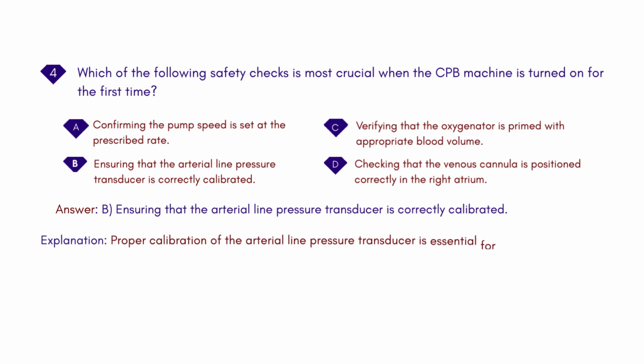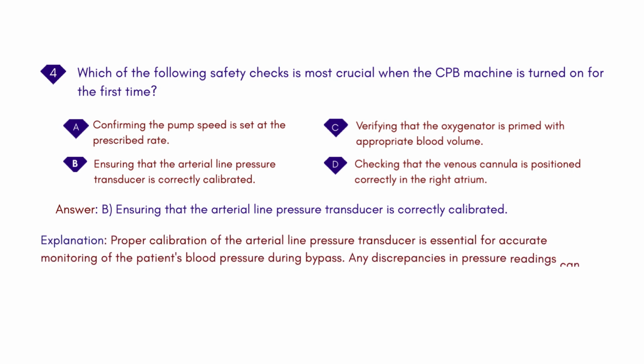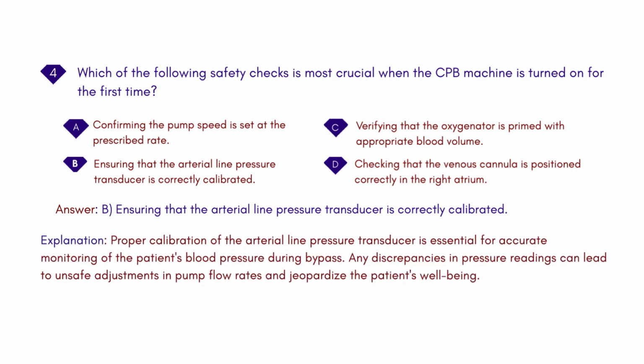Explanation: proper calibration of the arterial line pressure transducer is essential for accurate monitoring of the patient's blood pressure during bypass. Any discrepancies in pressure readings can lead to unsafe adjustments in pump flow rates and jeopardize the patient's well-being.